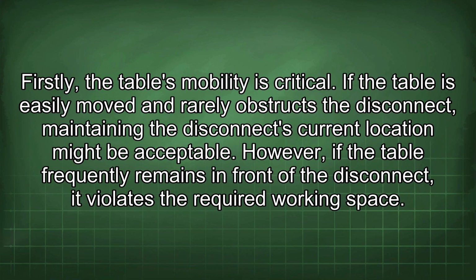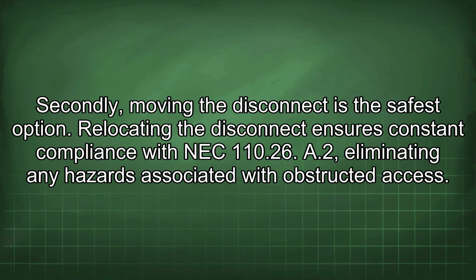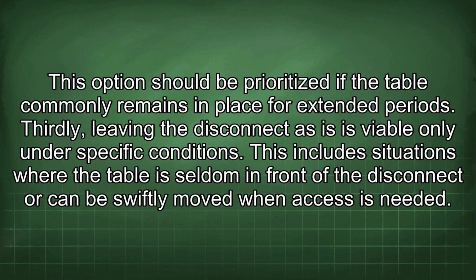Firstly, the table's mobility is critical. If the table is easily moved and rarely obstructs the disconnect, maintaining the disconnect's current location might be acceptable. However, if the table frequently remains in front of the disconnect, it violates the required working space. Secondly, moving the disconnect is the safest option. Relocating the disconnect ensures constant compliance with NEC 110.26.A2, eliminating any hazards associated with obstructed access. This option should be prioritized if the table commonly remains in place for extended periods.